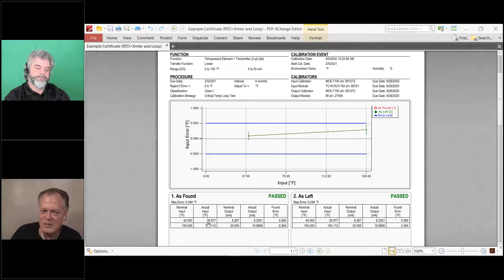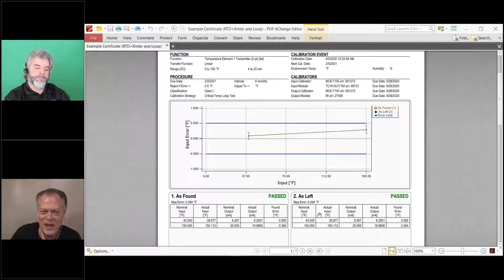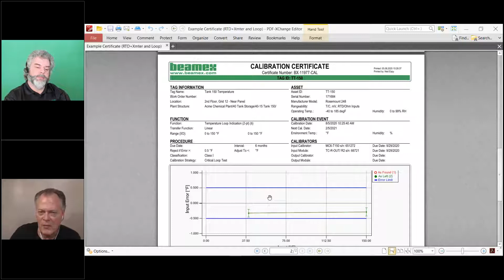If you had your paper form, you would have written down these kind of numbers. Notice this is out to 3 decimals on the temperature and 4 decimals on the milliamps. That's an example of the transmitter and probe married together. And then here's the loop. The loop was below. So there definitely is an offset between the 4 to 20 and what's being measured in the field. We've got some work to do to make this look a little better. But this is kind of real stuff.